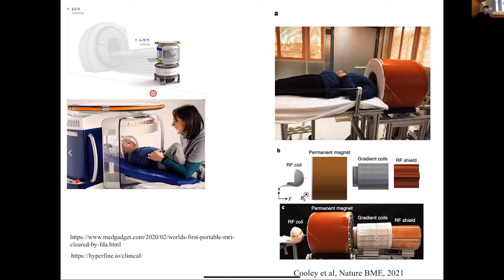A student asks about coil size and sensitivity. Smaller coils placed close to the body receive signal from a local region and see less noise than a large body coil far from the tissue. The trade-off is depth penetration — for larger patients, small coils may not reach deep structures. There's a trend toward wearable coil arrays integrated into jackets so each coil captures local signal with minimal noise.